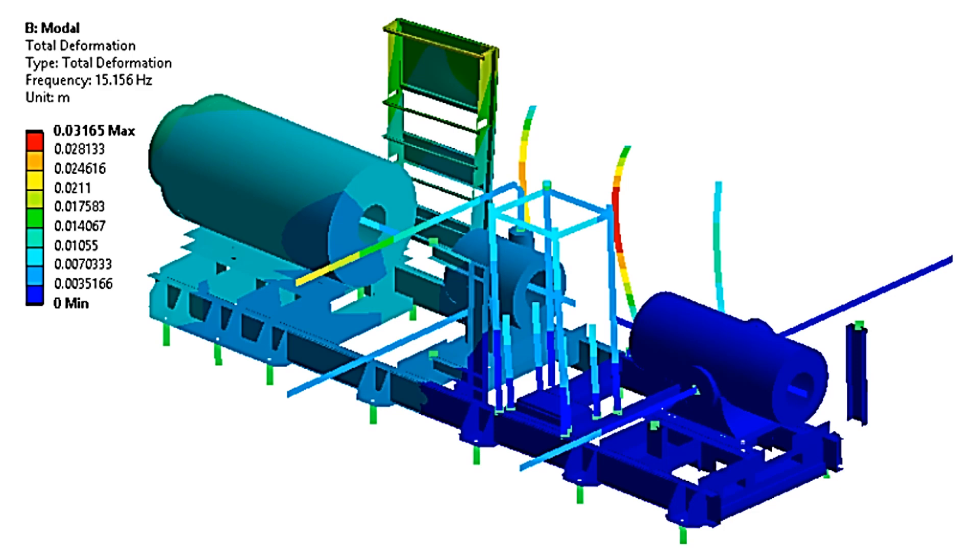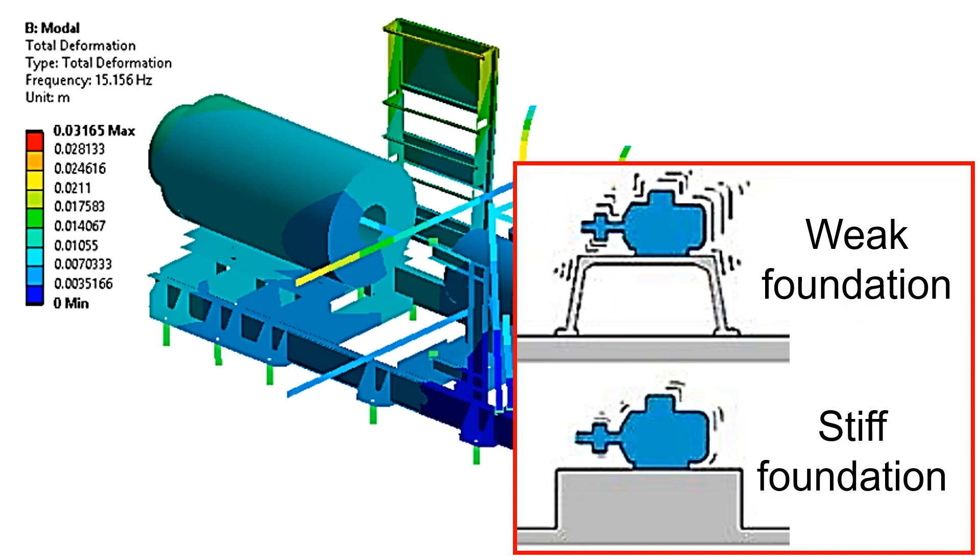In case of complex machine arrangements, conducting modal analysis can be beneficial for assessing the natural frequencies of the machine setup. The modal analysis provides insights into whether the foundation is weak or stiff based on the understanding of natural frequencies.